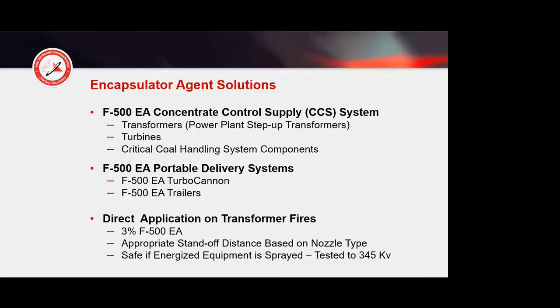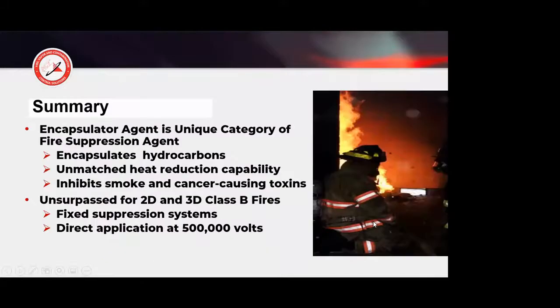So, you know, what we push and promote for the concentrate control systems is mainly the 3-dimensional Class B fires. And we promote a manual backup type system as well as training. So it's a unique category of agent. It encapsulates the fuel molecules. This says hydrocarbons, but it's actually carbon materials, unburnt carbons, the hydrocarbons and polar solvents. Unmatched heat reduction, inhibits smoke and cancer-causing agents. Does very good 2D and 3D fire protection capabilities, and you can do a direct application in an environment up to 500,000 volts. And that again is in the New York's SOG.